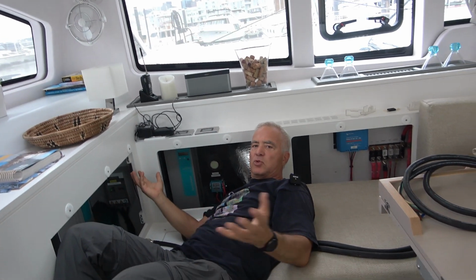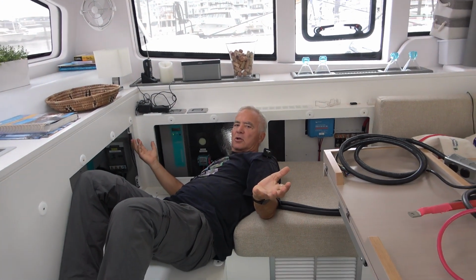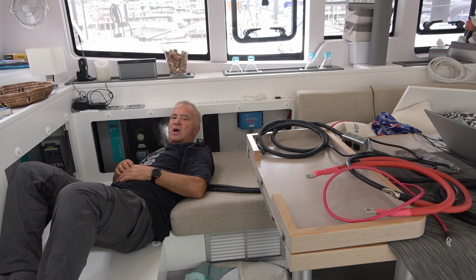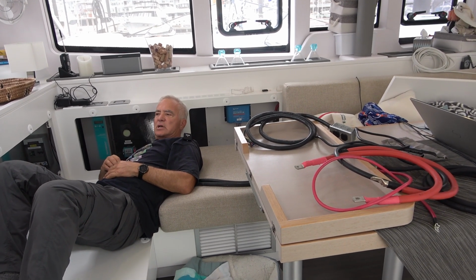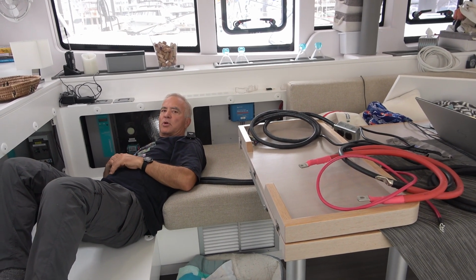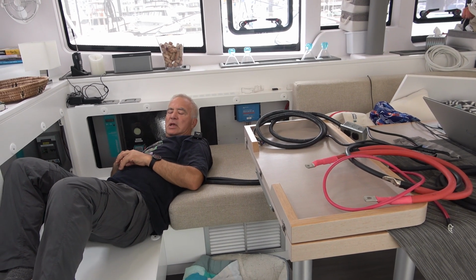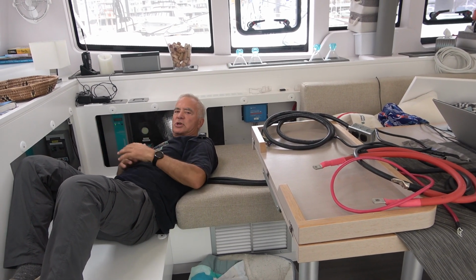So by adding the third one, three of them at 80 amps will give me 240 amps of charging at 25 volts, which is perfect because that will really load up my generator to 80% load, which is also the sweet point for the generator.